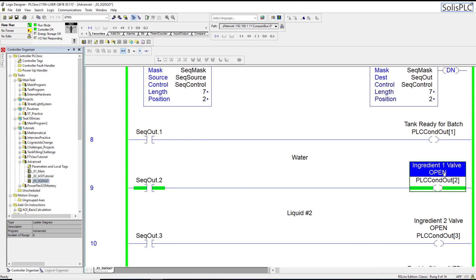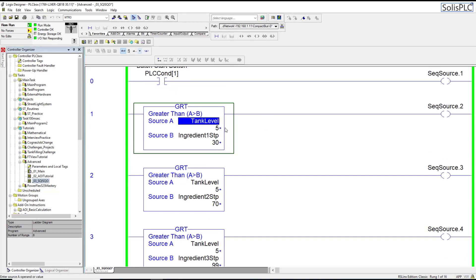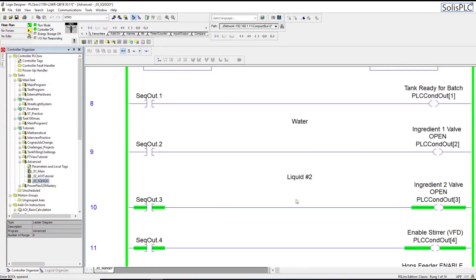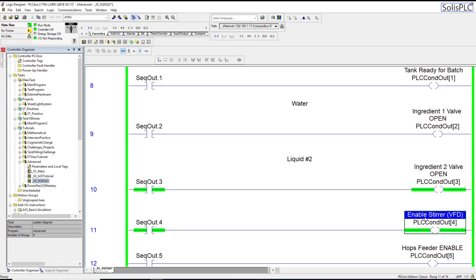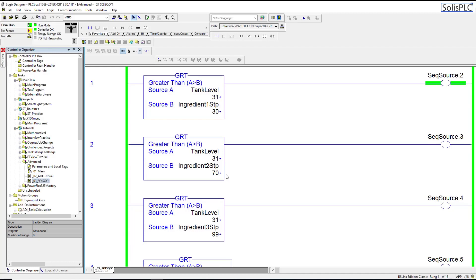Step two is to fill the tank with water. The ingredient valve tied to the water supply is open. As the water fills the tank we see an increase in tank level - think of this as an analog sensor reading the values - it increases to 10, 20, 30, and at some point it goes beyond a certain set point. At that level we send an output indicating we've reached enough water level. Sequence number two says turn off that valve and open the supply valve for the second ingredient. Now with the second ingredient we not only need to keep adding it, we also need to stir the tank.